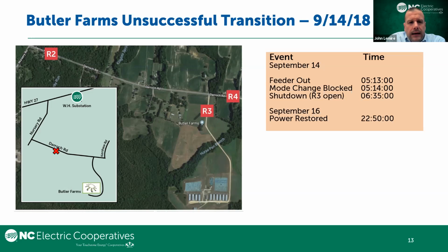When we simulated the testing during commissioning, including loss of phase and operation, what we didn't realize was that in this specific type of recloser, we were using an alarm feature to indicate an issue as one of the triggers for the microgrid. Because it was simulated, we didn't realize that one of the events that could generate this alarm, which says we've got a recloser issue and cannot transition the microgrid, is a loss of AC alarm. And loss of AC grid power is inherent to a microgrid needing to operate.